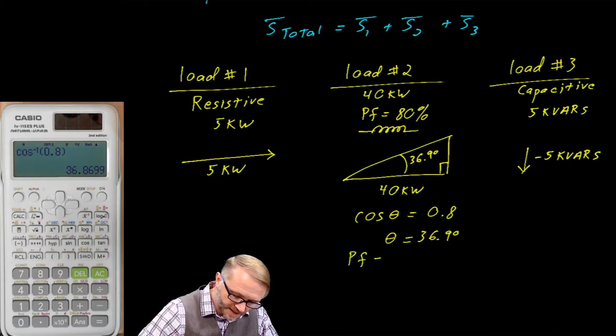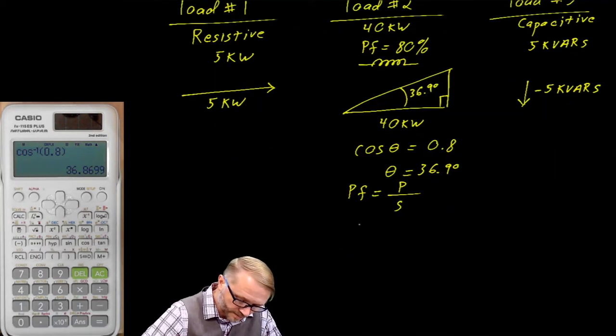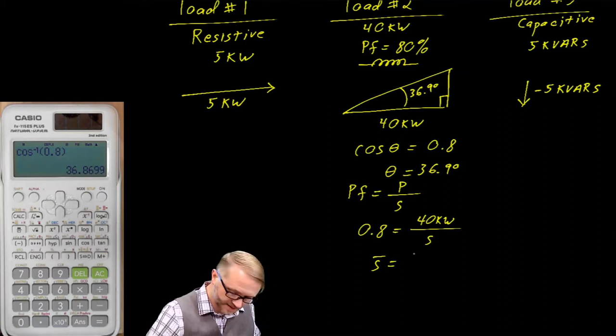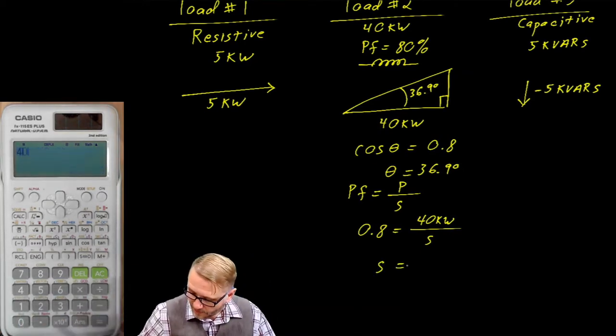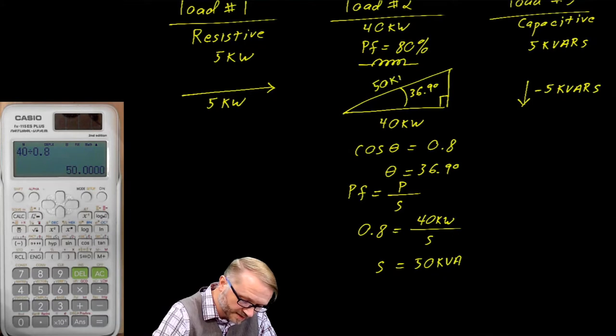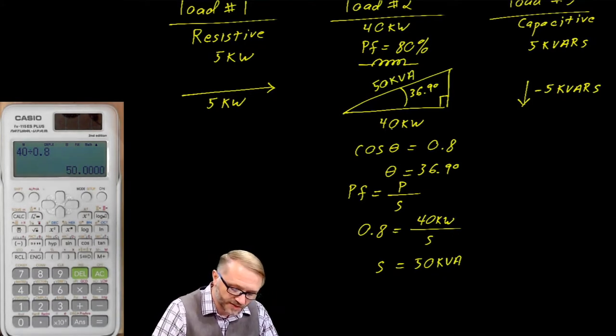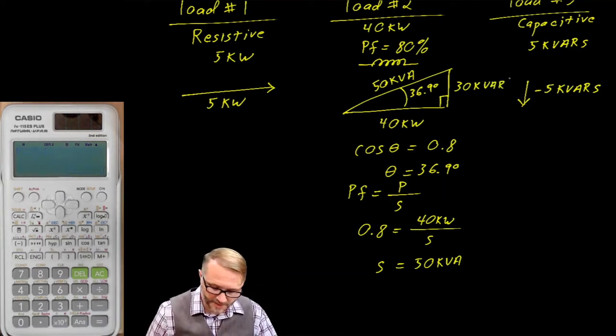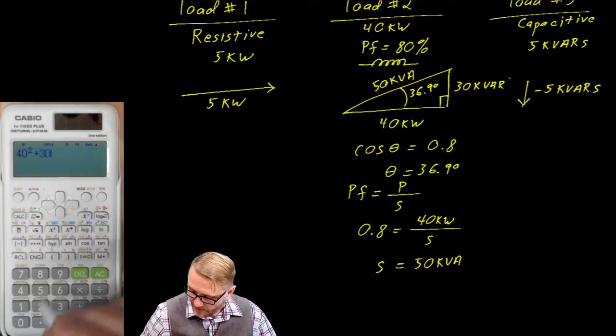We also know that power factor is the ratio of real power to apparent power. So 0.8 is equal to the real power, 40 kW, over the apparent power — that's a scalar, not a vector. So that's 40 divided by 0.8, which gives us 50 kVA. You may recognize this as a 3-4-5 triangle, meaning this side is 30 kVars. You can verify that using the Pythagorean theorem: 40 squared plus 30 squared, take the square root, equals 50.